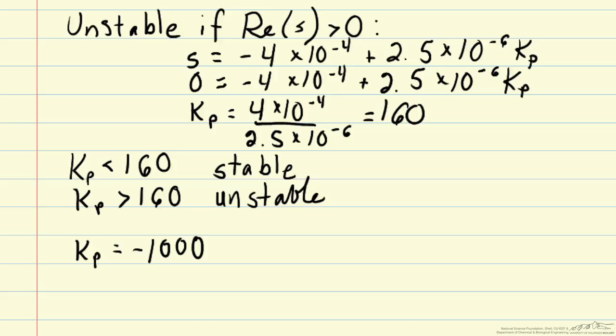There's a reason we consider negative numbers here. We have a negative gain on our process, and that is going to require that we have a negative gain on our controller. There's a physical reason for that. Stream 2 coming into the tank does not have any of species A, according to our set point and steady state values. By increasing the flow rate of w2 into the tank, we are diluting x in the system. If we are too low in terms of our value of x in the tank relative to the set point, we need to turn down the flow rate going into the tank. That's what this negative gain on the system is going to give us.